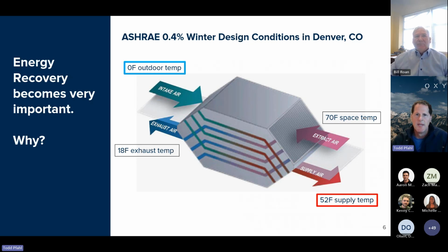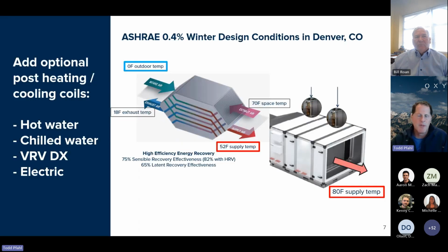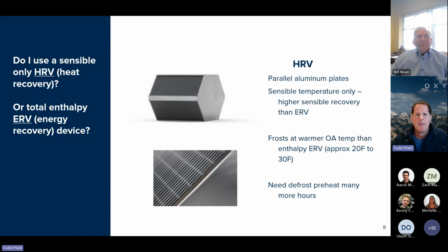So these are very efficient. It's not uncommon to see supply air temperatures coming off the heat exchangers in the upper 40s to low 50s. So what that does for us is now it's much, much easier to further heat that outside air in cold temperatures. So now we've got 50 degree air. We can utilize hot water coils, VRV, DX, heat pump coils, electric coils to further raise the temperature of that air. So again, we're just improving the overall efficiency of the system.